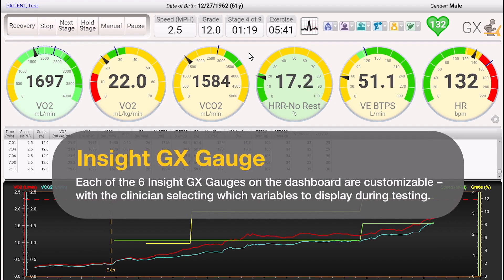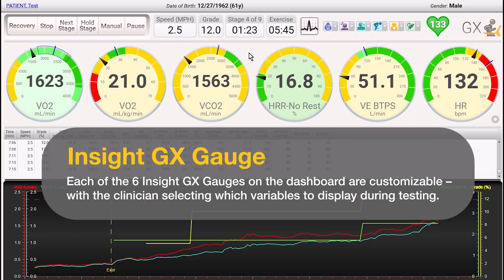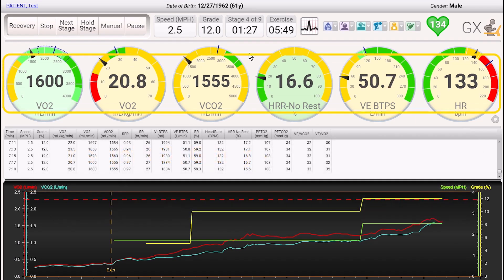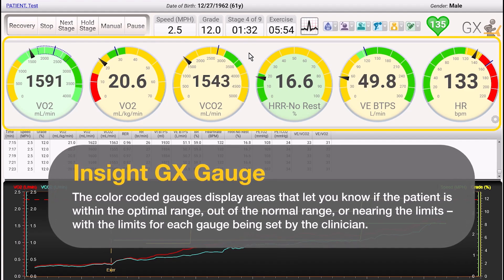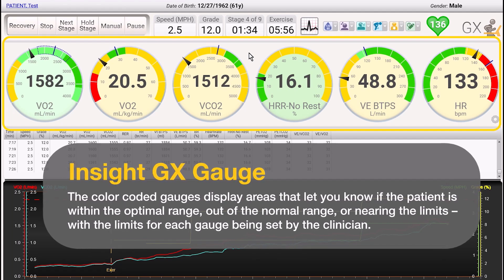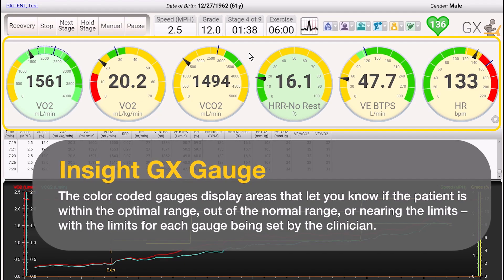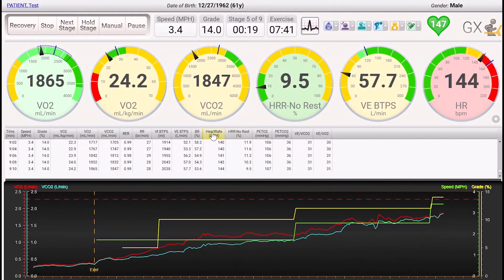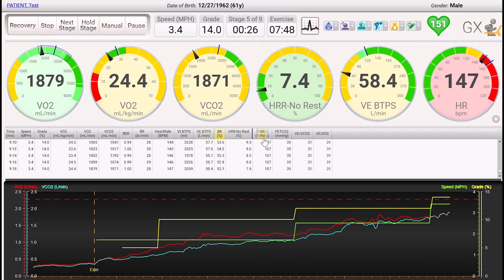Each of the six InSight GX gauges on the dashboard are customizable, with the clinician selecting which variables to display during testing. The color-coded gauges display areas that let you know if the patient is within the optimal range, out of the normal range, or nearing the limits, with the limits for each gauge being set by the clinician. All the variables in the test grid are user-selectable and allow you to add or remove a variable or click and drag a variable to change its position on the grid.